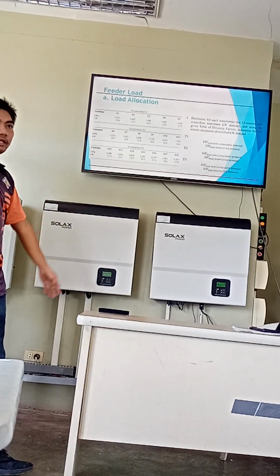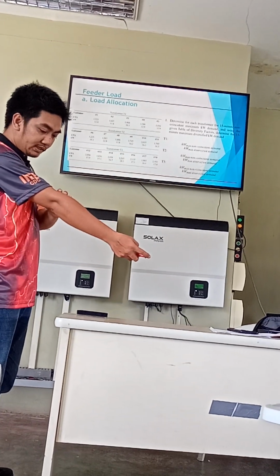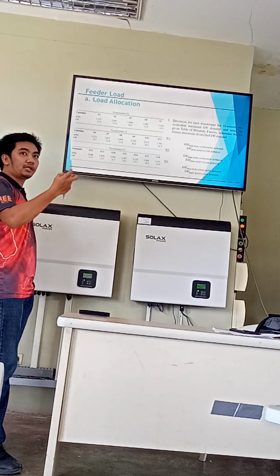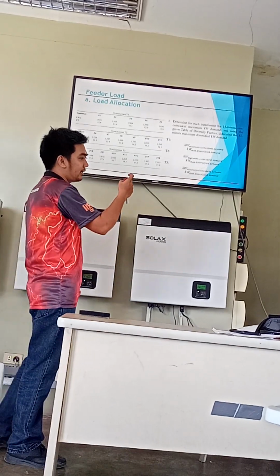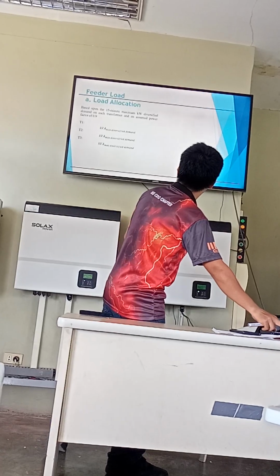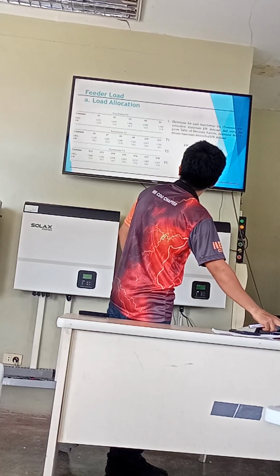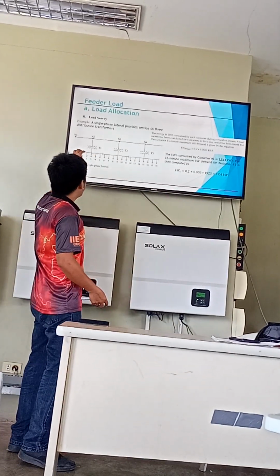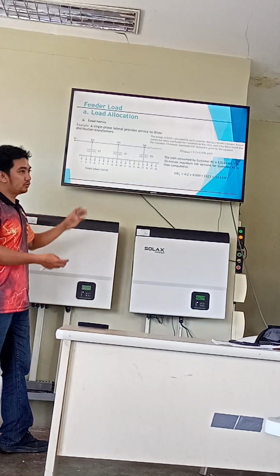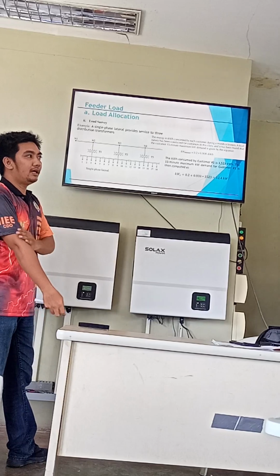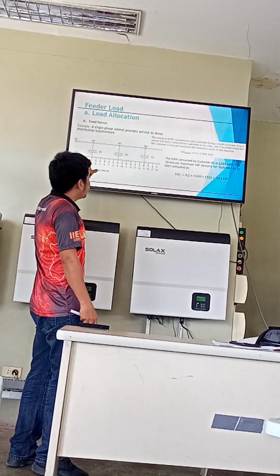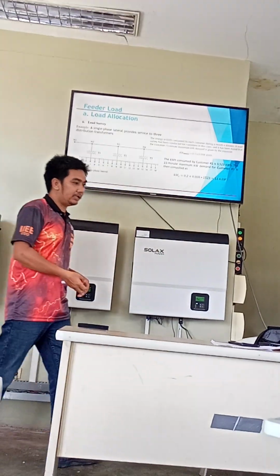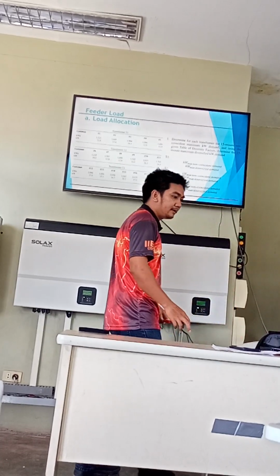With this information, we can now determine the diversified demand per distribution transformer. What we want to find is the loading per transformer. If you simulate or analyze each individual connected load, your system becomes larger, and you don't have information on the distance between the transformer and the load. But if we look at the DT, the loads are lumped at the transformer, and the analysis would be easier.